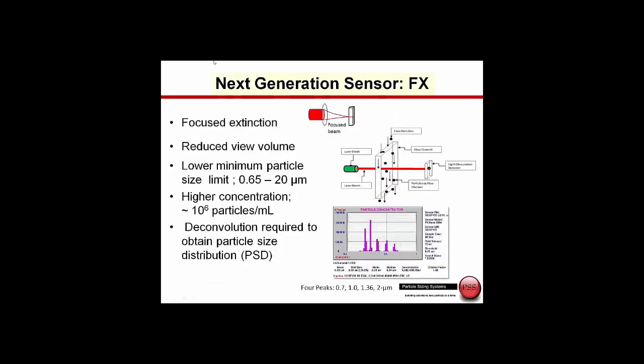As we wanted to improve the sensitivity to smaller particles, the change that was made is that we started focusing the laser beam. As we focus the laser beam to the center of the measurement zone, we now have higher laser intensity and we can measure smaller particles. The FX sensor is a focused extinction sensor. It can measure from 0.65 up to about 20 microns. Since we are now focusing at the center of the measurement zone, we actually have to collect many pulses from many particles and feed it through a deconvolution algorithm to build up the complete particle size distribution.